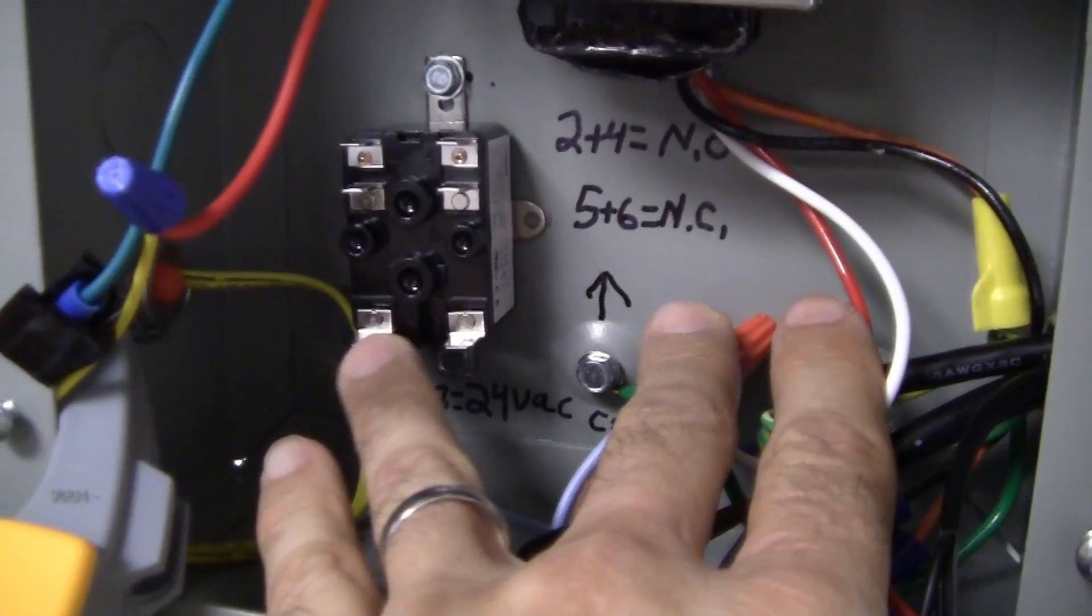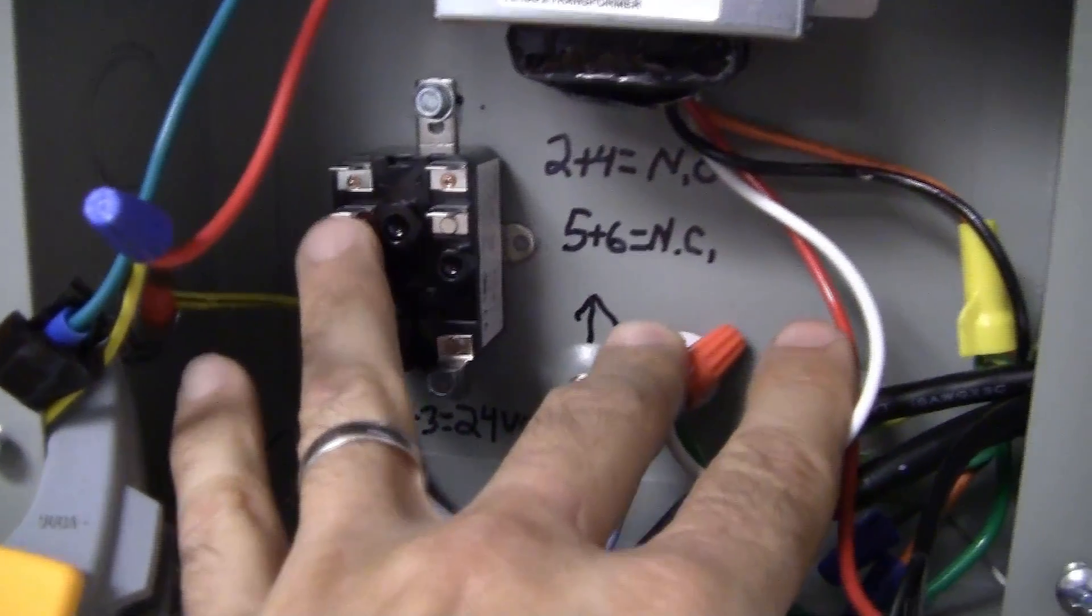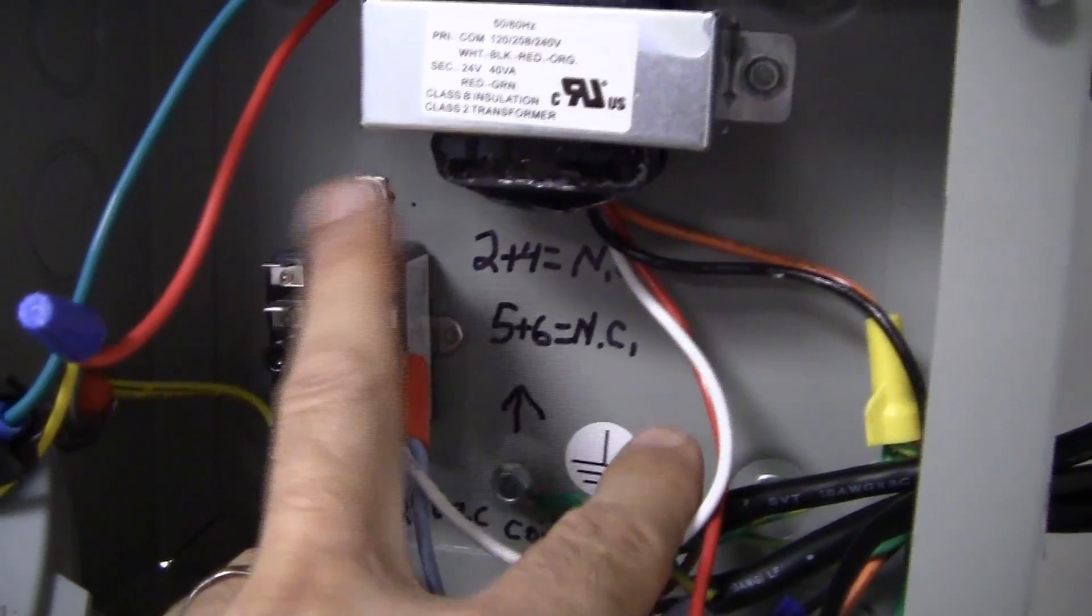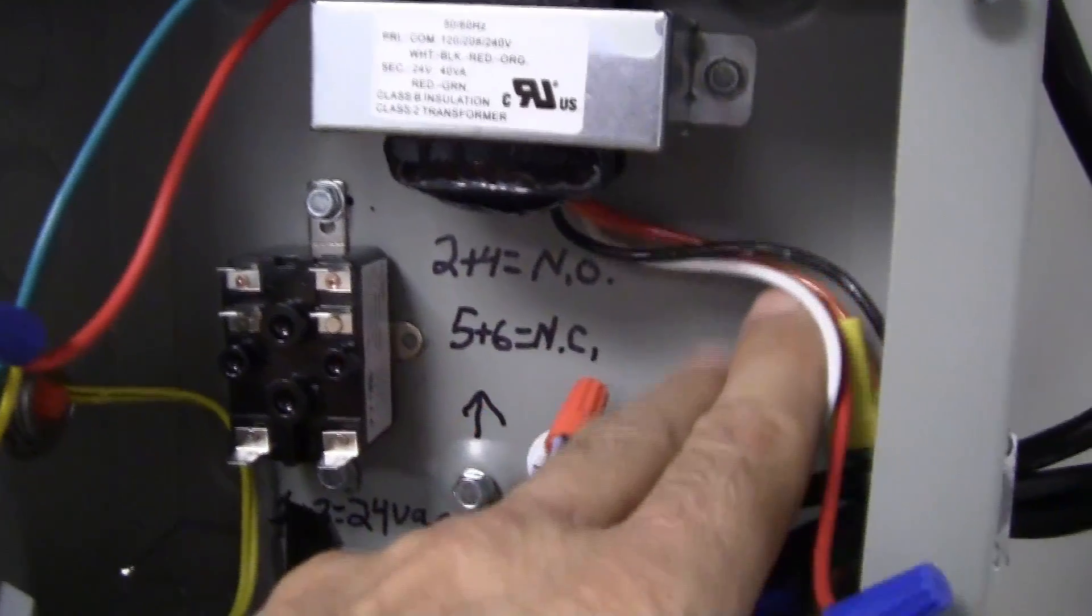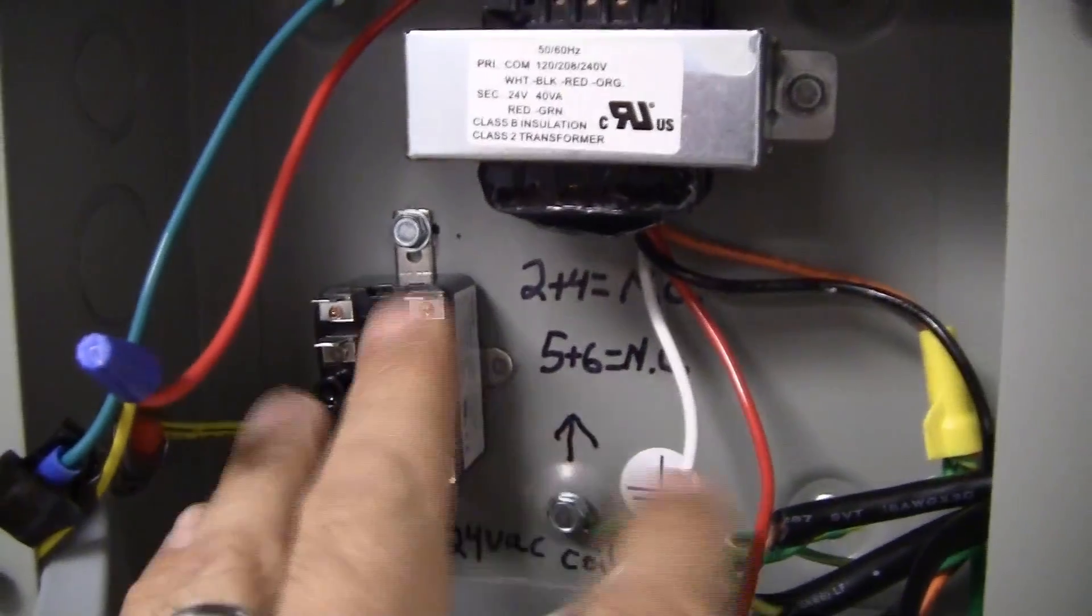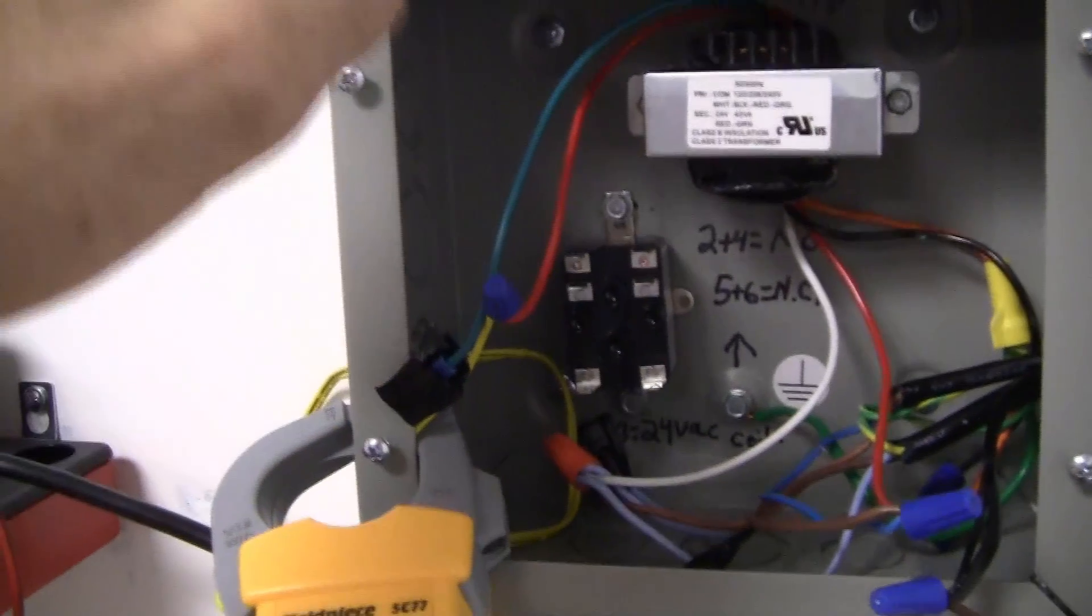When you look at my relay these two lines here at the bottom is my 24 volt coil, these next two lines up are normally closed and these next two terminals are normally opened terminals two and four. When the relay opens because the safety circuit opens because we've reached a high level in the float it's going to shut that power off going to the mini split evaporator.